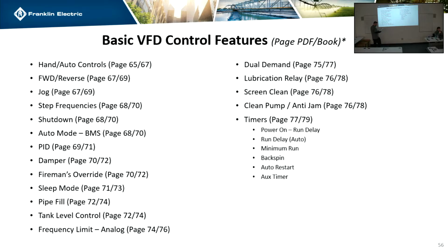All right, so this is the page that's going to cover the keypad again, and then it's going to go over how to set up specifically your hand and auto and how they're different. Normally what we do is hand mode is not PID, auto mode is PID. HVAC's a little bit different because you don't necessarily use PID for everything. So what you could do is auto would be your automatic like terminals and 0 to 10, and then your hand switch would all be keypad, so that you could always pull it off the system and temporarily run it however you wanted.